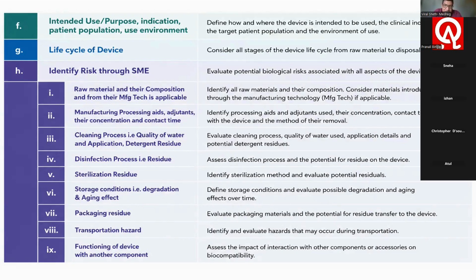depending on the presence of the residues generated from the sterilant, that is ethylene oxide, in terms of ethylene chlorohydrin and ethylene glycol, and ethylene oxide itself. If those residues are present in your device, it is also toxic to the patient. That also depends on the intended claim, for example child, adult, everything. So it is required to be assessed whether those residues are within the limit or not.